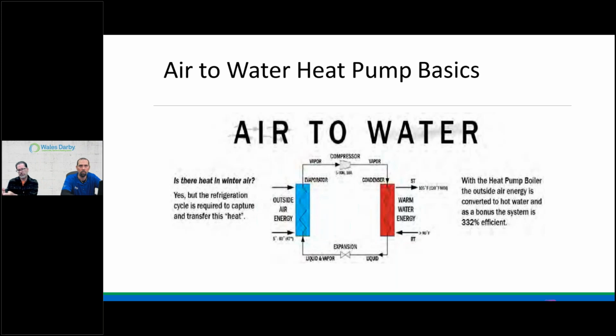You're dealing with other pieces of equipment where we're throwing away money, right? So if we go back to the other slide where we have the arrows, the oil, the high temperature condensing, non-condensing in the 80s, for every dollar of energy, you're throwing away 18 cents. So now understanding lowering water temperatures, marrying it with emitters, and using something like maybe this air to water heat pump, I'm producing 250% efficiencies. That sounds like a benefit to my wallet, right? And I'm not giving up comfort. And that's where, again, we sit: the energy and comfort business, right? That's really where we're in.